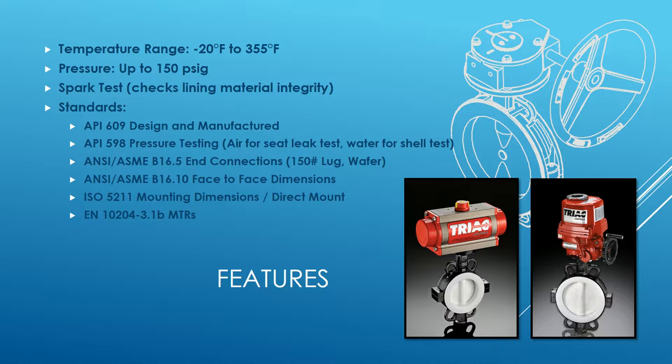The shell test meets B16.5 end connections — that's 150 pound lug and wafer. It's important to point out that it does not meet class pressure ratings, but it does have those end connections. It meets the 150 psi gauge limit for pressure; it does not go up to 285 psi as class 150 would. It also meets B16.10 face-to-face dimensions.